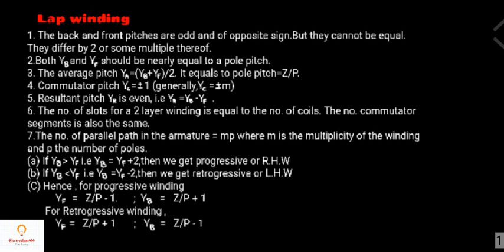The resultant pitch Yr is always even; for lap winding, resultant pitch equals back pitch minus front pitch. The number of slots for two-layer winding equals the number of coils. The number of commutator segments is also equal to the number of coils. The number of parallel paths in the armature equals m times P, where m is the multiplicity factor of the winding and P is the number of poles.